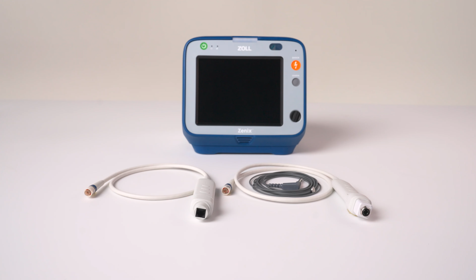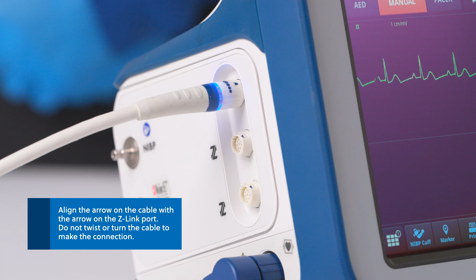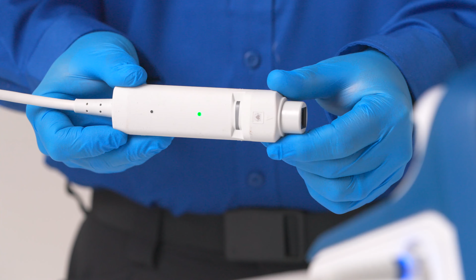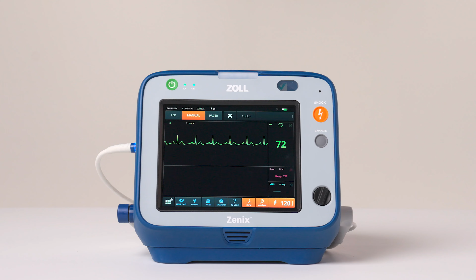Let's start with invasive blood pressure monitoring. First, connect the IBP interface cable to one of the Z-Link ports. When properly connected, the blue LED at the Z-Link port illuminates. In addition, the round green LED on the IBP cable also illuminates. Once the transducer is attached to the interface cable, a green sensor LED bar illuminates and the message "Zero Probe" appears in the numeric display window for that invasive pressure channel.